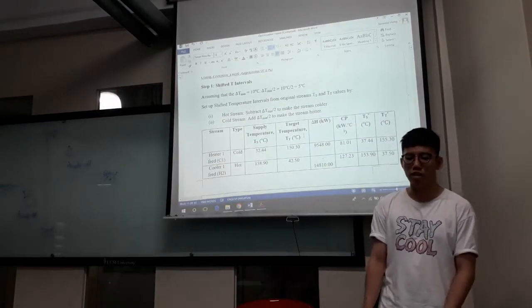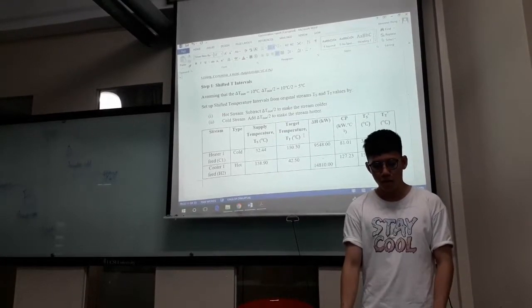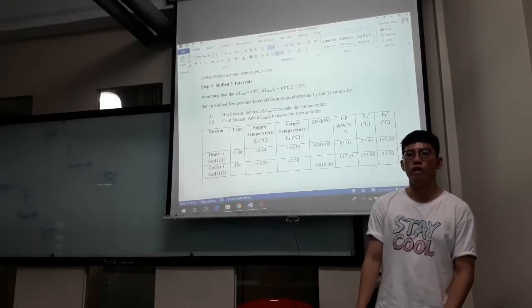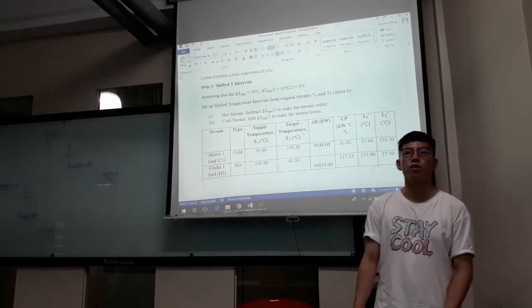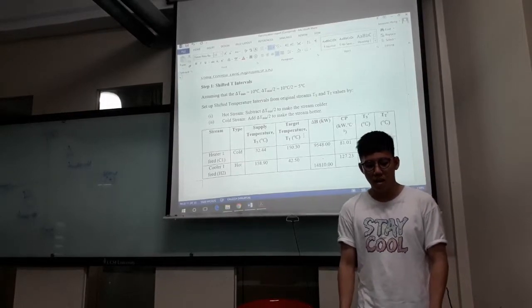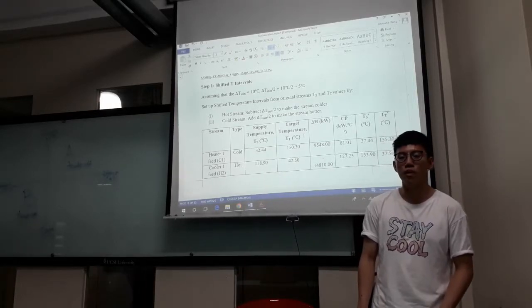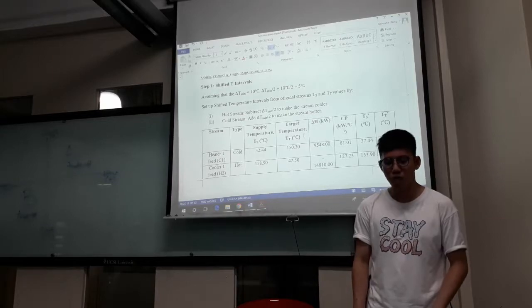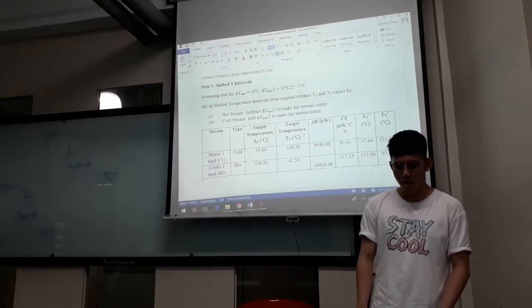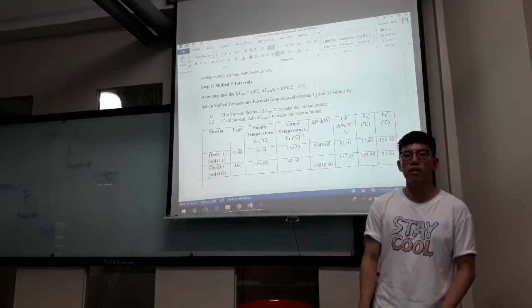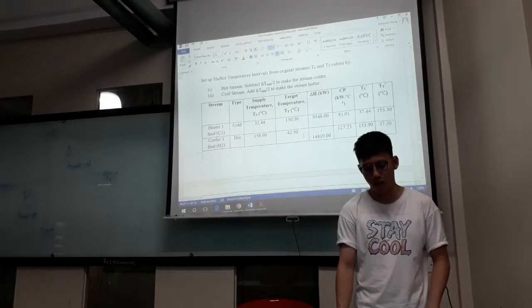In order to identify the pinch location, I am using the PTA method — the problem table algorithm. The first step is to find the shifted temperature intervals. To find the shifted temperatures, I need to find the shifted supply temperature and the shifted target temperature. Assuming the minimum temperature approach ΔTmin is 10°C, we divide by 2 and get 5°C. For the hot stream, I subtract 5°C to make the stream appear colder, and for the cold stream, I add 5°C to make the stream appear hotter, giving this table.